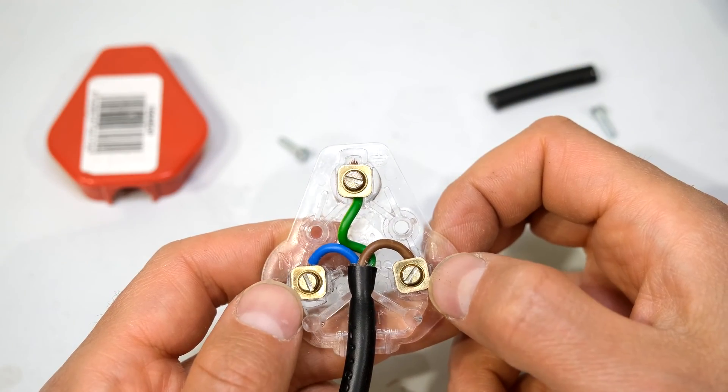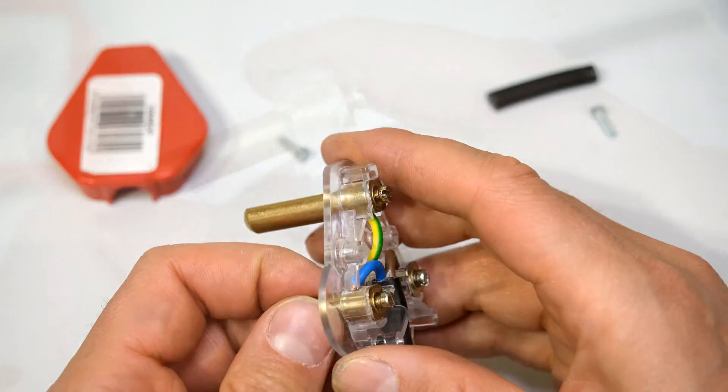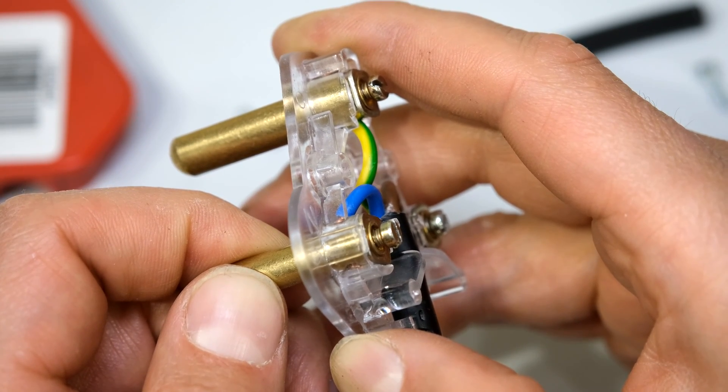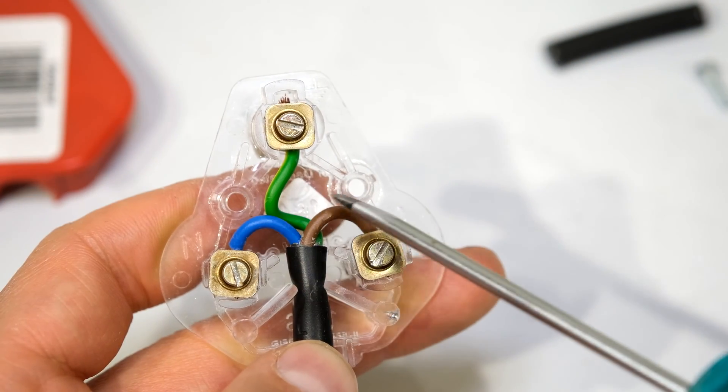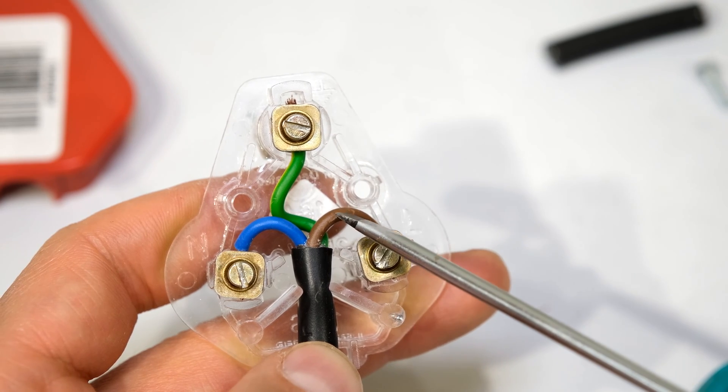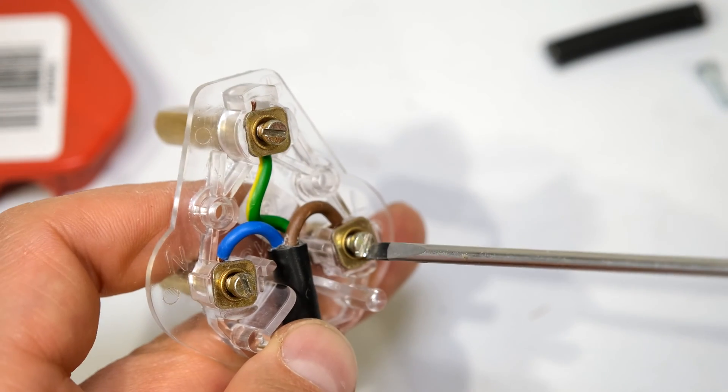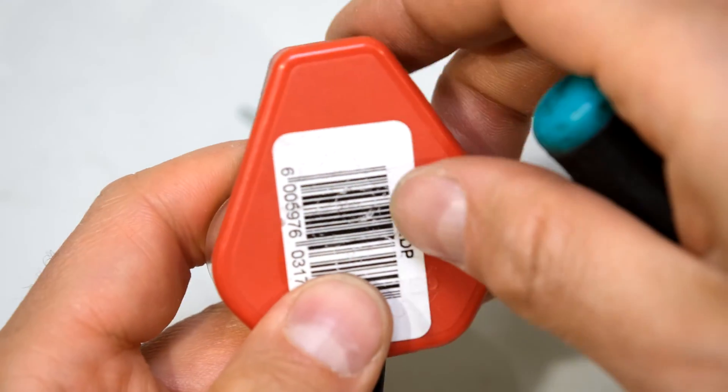Just before you close it, make sure these prongs are seated correctly. For example, that is not seated correctly, but now it is seated correctly. Make sure none of these wires are sitting on the screw post, or they'll get crushed when you put the plug top on. Do a last check. Make sure everything is tight. And now put your plug top on.